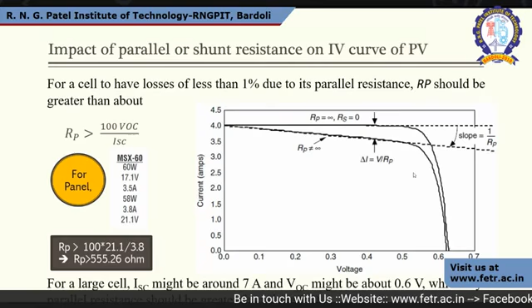Obviously, 21 volt is higher compared to 17, so 21.1 is the VOC, and in this case, our RP is greater than 555.26 ohm. So there is less possibility to divert the current through RP. For a particular large cell, it might be 7 ampere and VOC might be 0.6 volt, which says that the parallel resistance should be greater than or about 9 ohm, because it can be applicable for cell, for module, for array, for string, and for entire power plant.